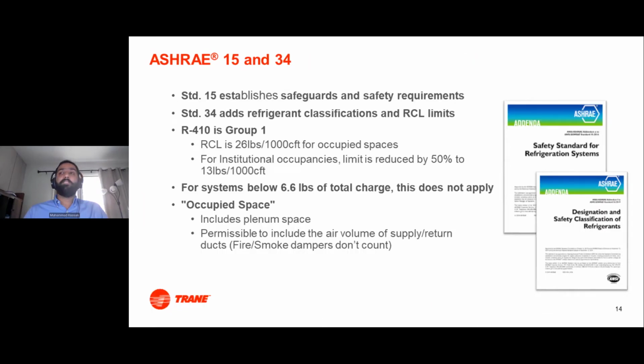ASHRAE 15 and 34, I see a lot of questions in the chat about how to navigate around the ASHRAE 15 and 34 regulations. For the uninitiated, standard 15 and 34 govern refrigerant in occupied spaces. R410A is a group A1 refrigerant. That's the standard for VRF systems in the industry. The term of concern in the code is the occupied space. It's important to remember that the occupied space does include the plenum space and the supply and the return ductwork. Typically, the ASHRAE 15 calculation is done by the engineer of record and facilitated by the manufacturer. So the manufacturers do have proprietary software that calculate the refrigerant charge for each of the circuits.